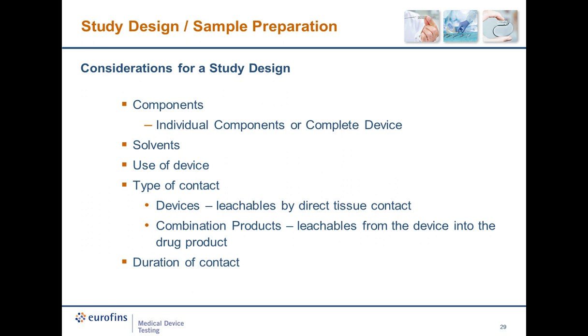When a sponsor designs a study to evaluate potential extractables and/or leachables from a device, there are many options, therefore many decisions that need to be made. The information gathering and risk assessment performed during the first step of the chemical characterization process will go a long way to aid the sponsor in making those decisions. Most of the information pertaining to sample preparation is currently detailed in ISO 10993 Part 12. The proposed revision of Part 18 contains conditions relevant to only an extractables or leachables evaluation, whereas the current Part 12 contains information on how to perform testing for a variety of endpoints.